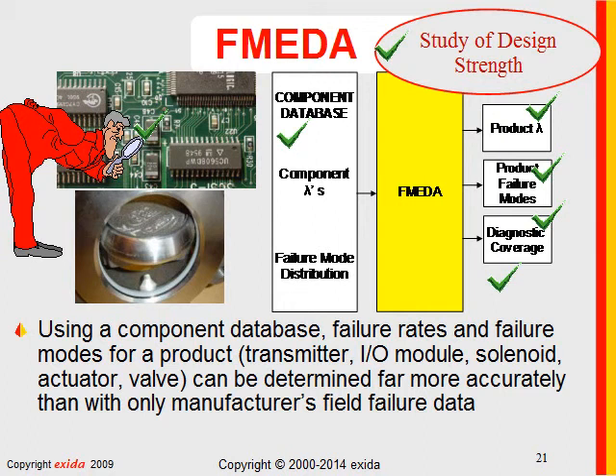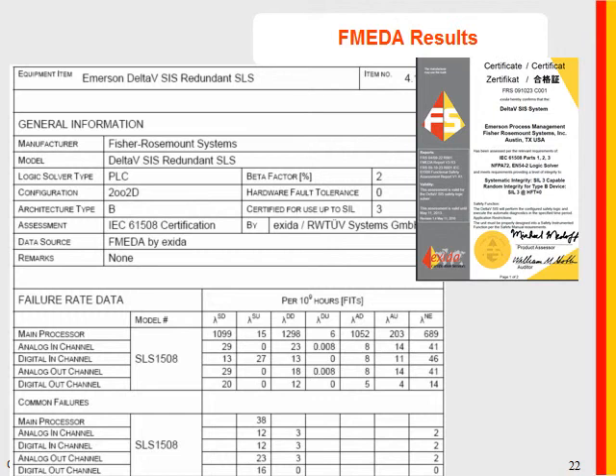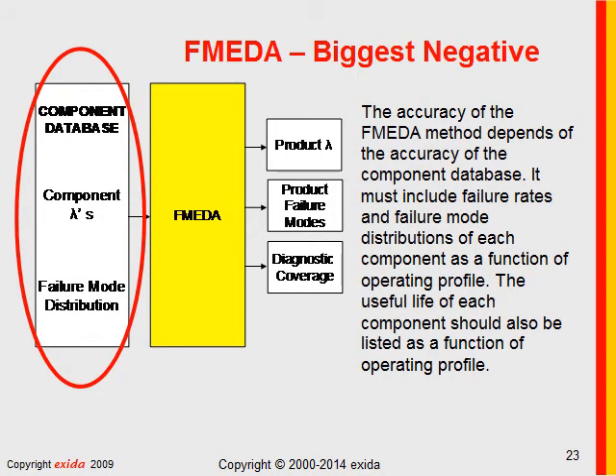Using a good component database, these numbers can be determined and predicted far more accurately than with only manufacturers' field data on previous products. FMEDA can generate very detailed results that clearly distinguish between different designs of mechanical, electronic, and electromechanical devices. The biggest negative of an FMEDA is the component database — garbage in, garbage out. The accuracy of the FMEDA depends on the accuracy of the component database, so it's very important that any component database be verified, or what we might call calibrated.